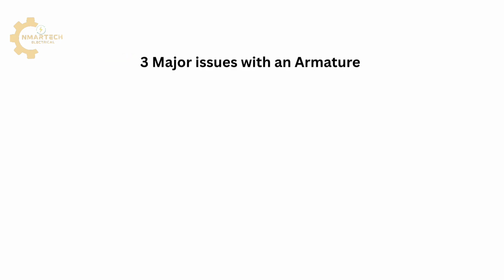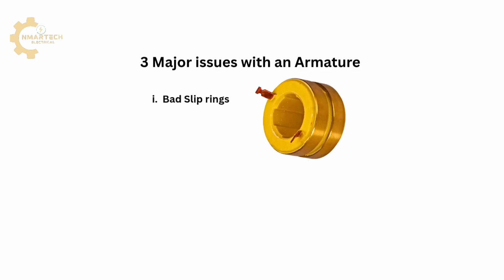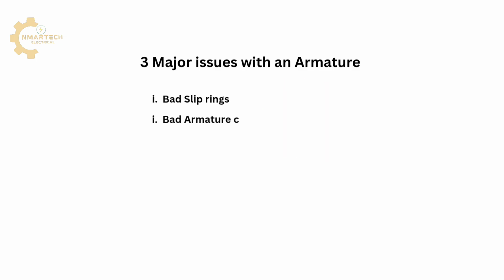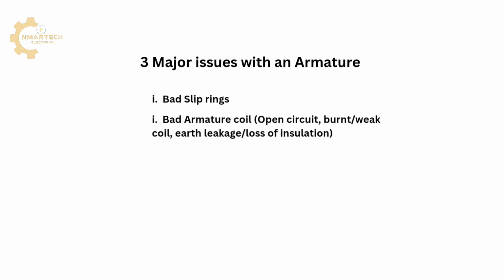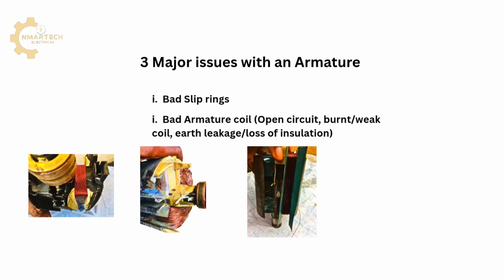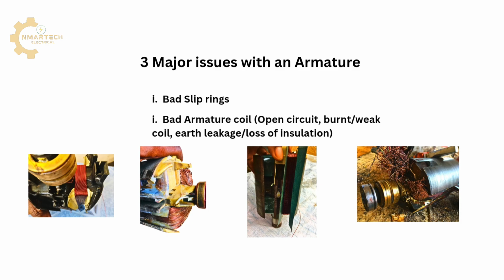The major problem of an armature that causes no voltage output is a bad slip ring. You can see the slip ring on the screen. Bad coil. The coil is bad when it's open circuited, burnt, weak, or has earth leakage. I have some videos on armature repairs and rewinding. I will drop their links in the description of this video.